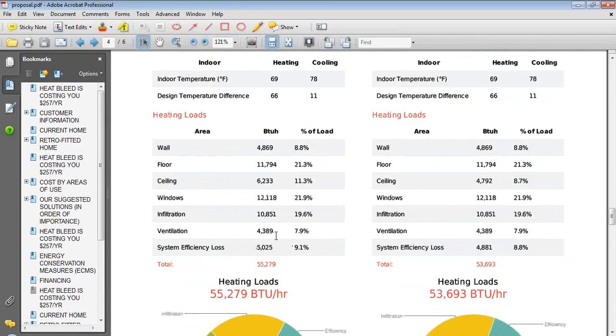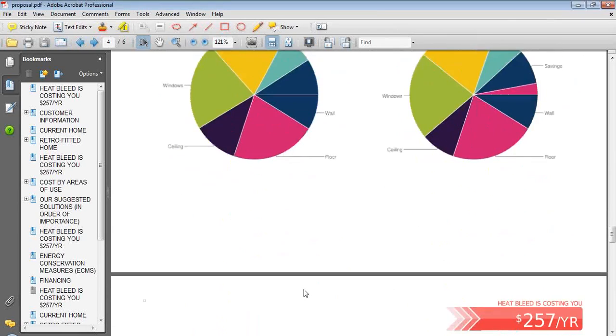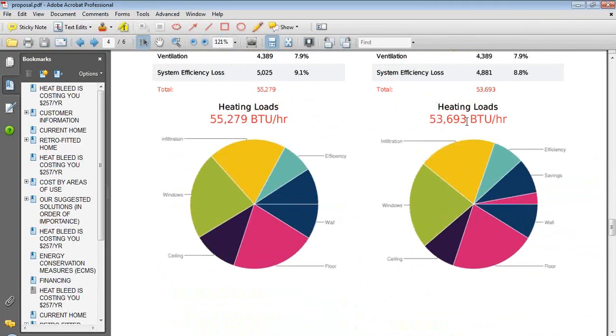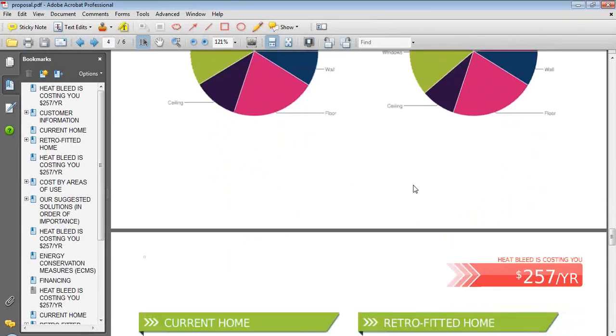So it's really, like I said, doing 2 load calculations side by side, showing you the improvements from one to the other. Right, and the load didn't change very much because the only thing I really adjusted that affected the load was the attic insulation going from R30 to R39. The furnace and AC choices have no effect on the load, right? They have an effect on the overall efficiency and dollars to operate the house, but they have no effect on my load calculation. So my loads are very similar in this case.